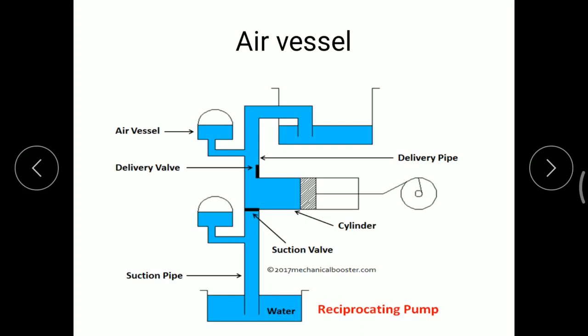We will discuss the first point, which is construction. An air vessel is a cast iron, banded, or fabricated steel chamber which contains compressed air at the top portion and water at the bottom portion of the chamber. As you can see, the void portion is represented by compressed air. It has an opening at the base through which water can flow. The air vessel is fitted either on the suction pipe near the suction valve, or on the delivery pipe near the delivery valve, or on both sides. It is always placed near to the cylinder.